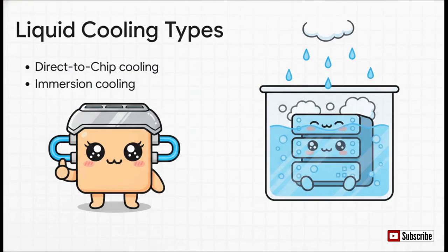There are two fascinating ways the industry is rolling out this liquid superpower. First, direct-to-chip or cold plate cooling. Instead of slapping a bulky metal heatsink and a loud spinning fan onto a chip, a closed-loop microchannel plate is bolted directly onto the CPU or GPU. Coolant fluid flows right through the plate, absorbing heat with closed-loop precision directly at the silicon level.